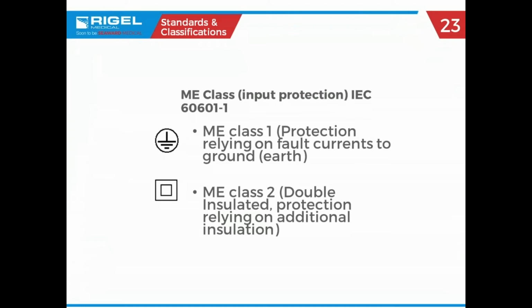So when you look on a piece of equipment, you can tell there's always these little symbols. So class 1 is always that ground symbol encased in a circle. That signifies a class 1 piece of equipment. The double insulated is the square within a square, kind of saying here's the chassis and there's another square around that, which is the plastic enclosure.